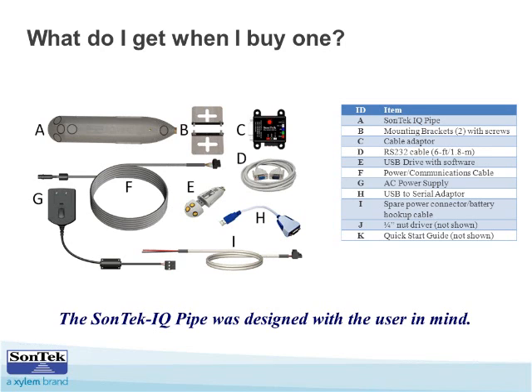Also, one thing that you need to pay attention to with this instrument, not unlike the others, is that the connector on this is not wet mateable like it used to be. It's much smaller, so therefore when you make that connection, it needs to be dry. Also regarding the conduit, we just give you the flying leads at the end, and then the wiring harness to connect it to. So if you need to chop this off and make it shorter, or chop it off and pull it through, you can do that, unlike our previous cables.